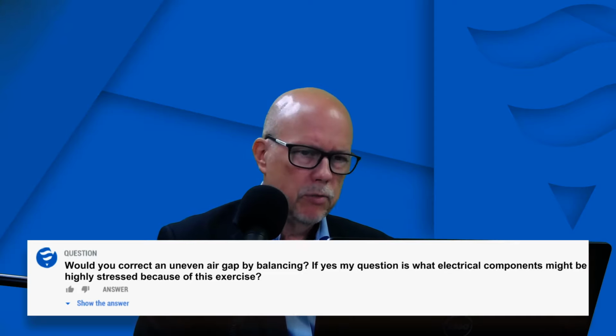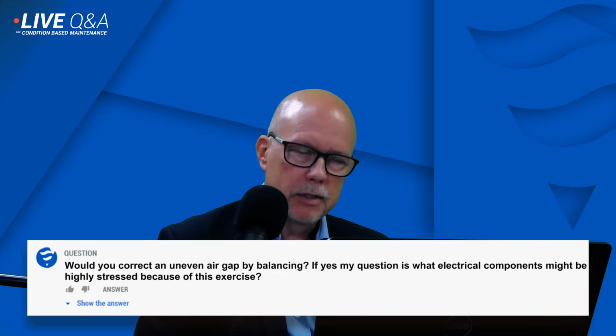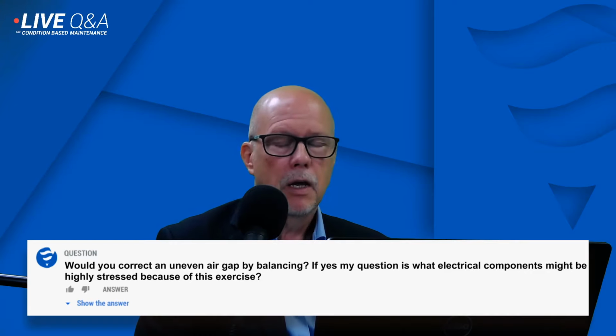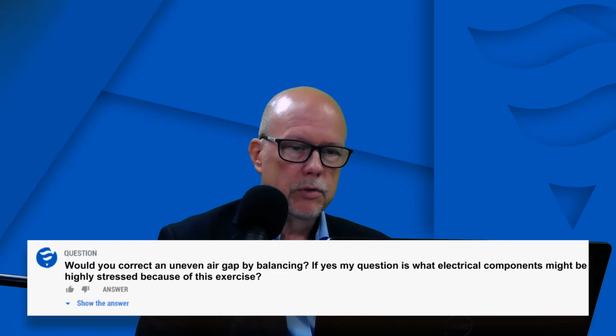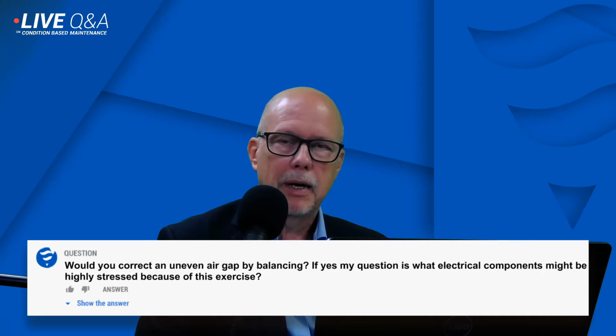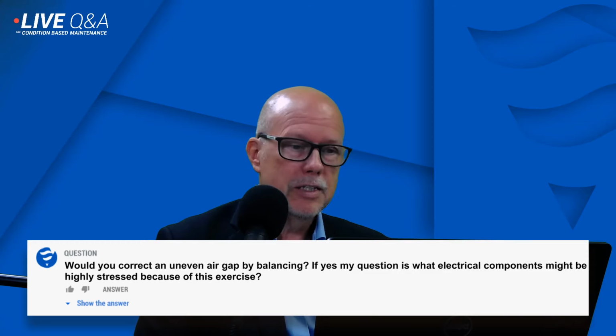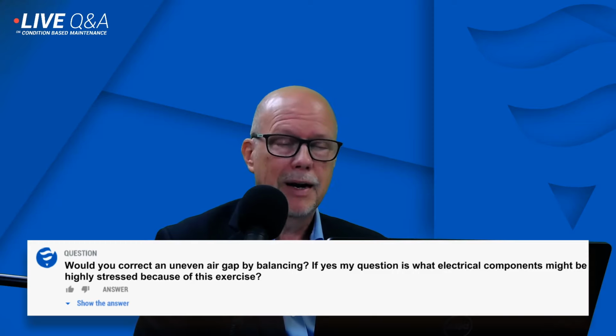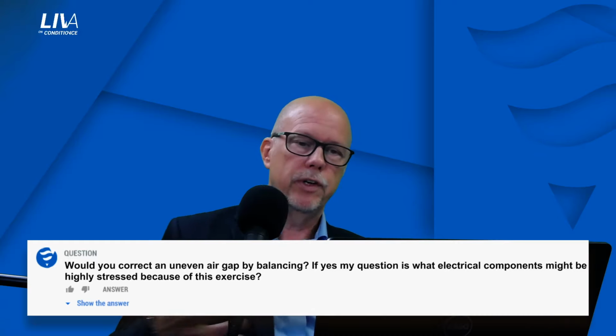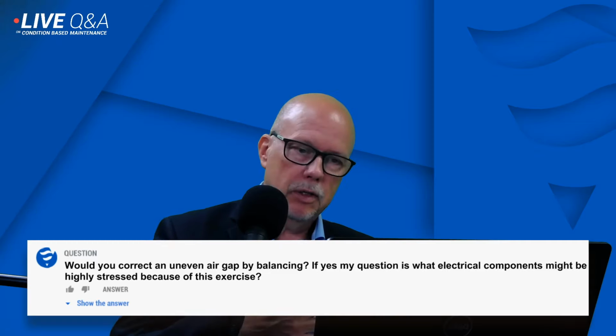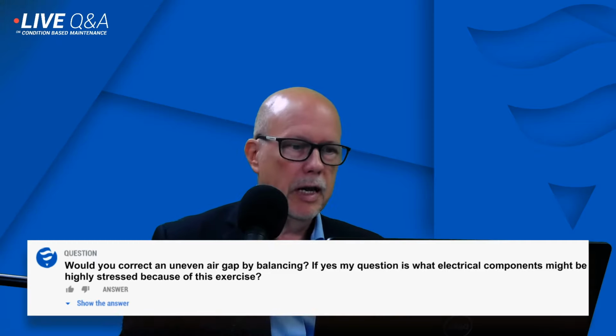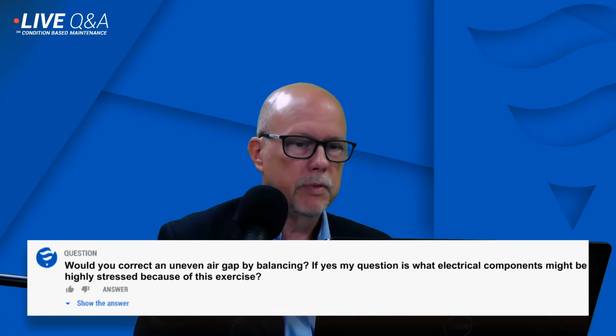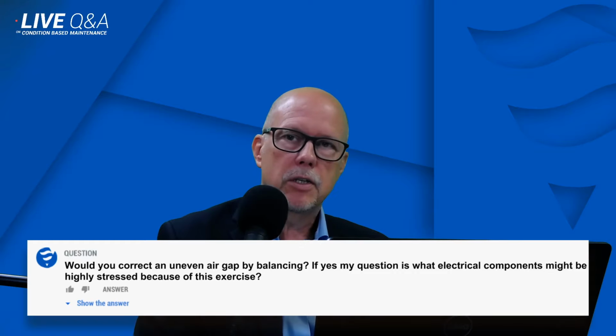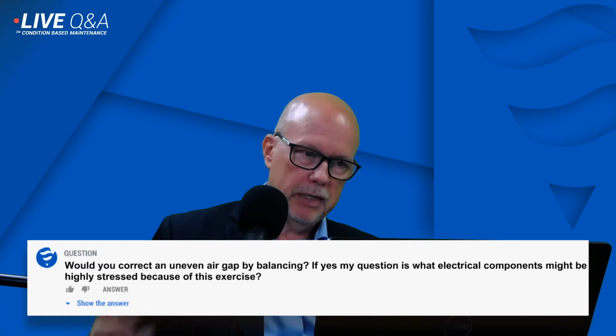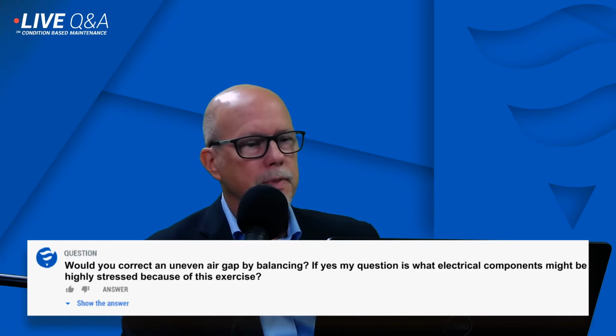And the question of the gentleman here was, well, would you correct an uneven air gap by balancing? And if yes, my question is, what electrical components might be highly stressed because of this exercise? Well, the answer to that is no. You do not correct an uneven gap by balancing, unless your uneven air gap is caused by excessive shaft displacement, whereas the rotor is moving around erratically inside the stator, and it's causing an uneven air gap. If that's the case, you might want to try balancing the rotor. But if your air gap is uneven only in one direction, causing this mechanical and magnetic center issue, balancing will not fix the problem.